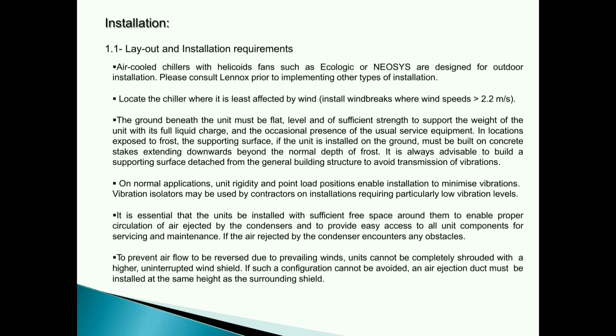Locate the chiller where it is least affected by wind. Install windbreaks where wind speeds exceed 2.2 m/s. The ground beneath the unit must be flat, level and of sufficient strength to support the weight of the unit with its full liquid charge, and the occasional presence of the usual service equipment.